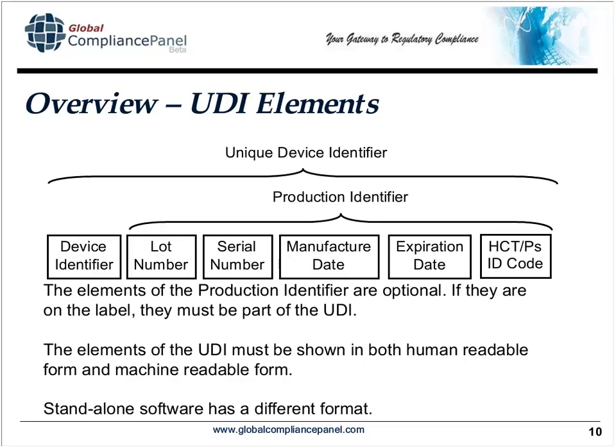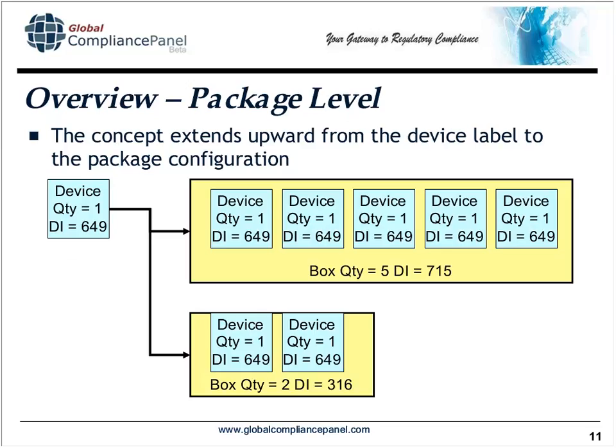For every device identifier — representing a version or model — you'll load the information into FDA's database. This concept extends upward from the device label to the package configuration. If you have a device sold in containers of one, and you also sell them in boxes of five, that box of five has its own device identifier. A box of two would have yet another device identifier. So you'll have many device identifiers associated with a device in all its standard packaging configurations.